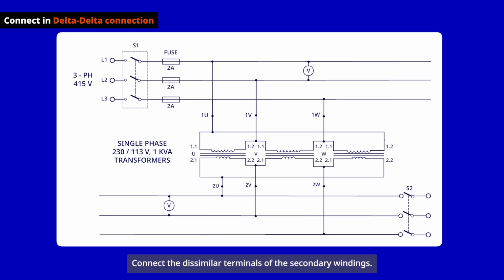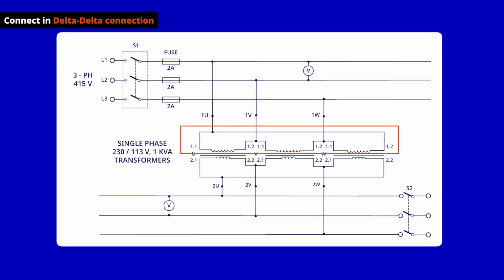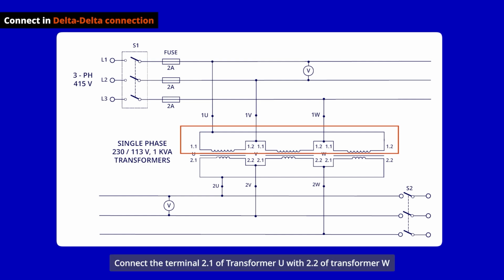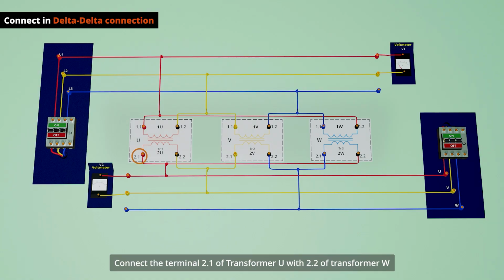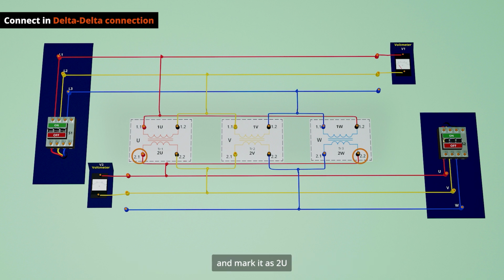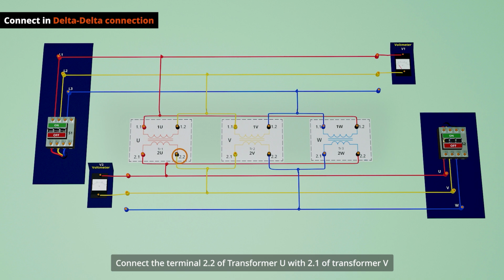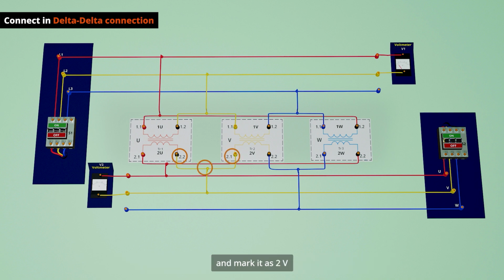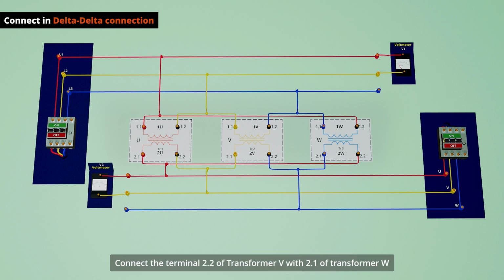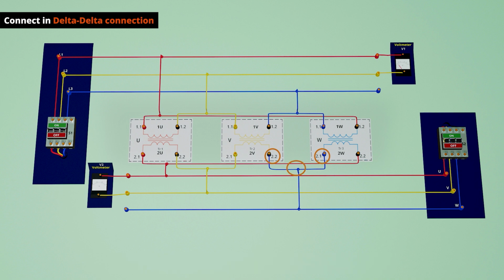Connect the dissimilar terminals of the secondary windings. Connect the terminal 2.1 of transformer U with 2.2 of transformer W and mark it as 2U. Connect the terminal 2.2 of transformer U with 2.1 of transformer V and mark it as 2V. Connect the terminal 2.2 of transformer V with 2.1 of transformer W and mark it as 2W.